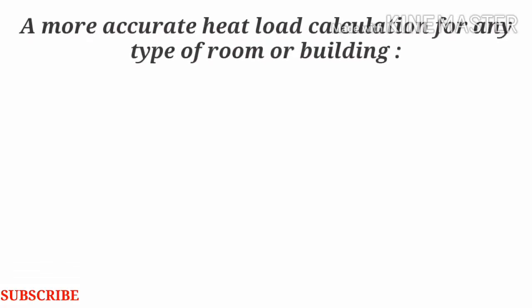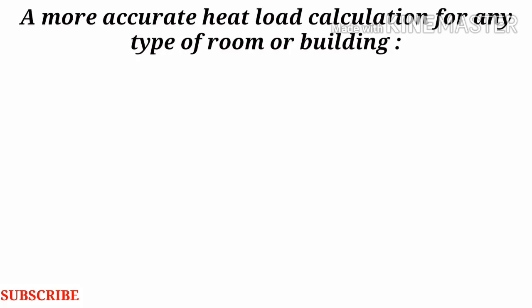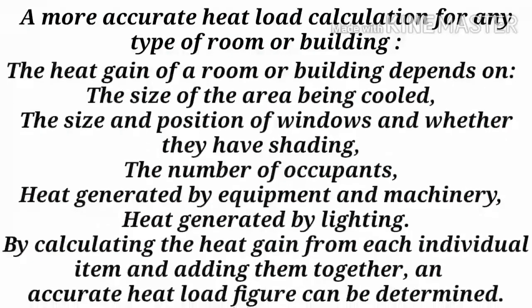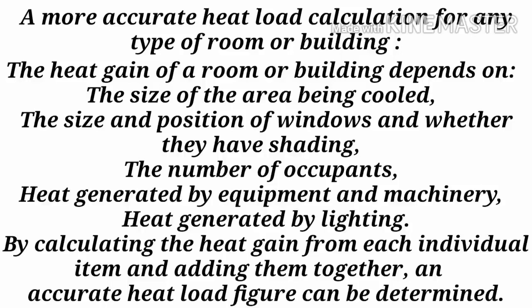A more accurate heat load calculation for any type of room or building: the heat gain depends on the size of the area being cooled, the size and position of windows and whether they have shading, the number of occupants, heat generated by equipment and machinery, and heat generated by lighting. By calculating the heat gain from each individual item and adding them together, an accurate heat load figure can be determined.